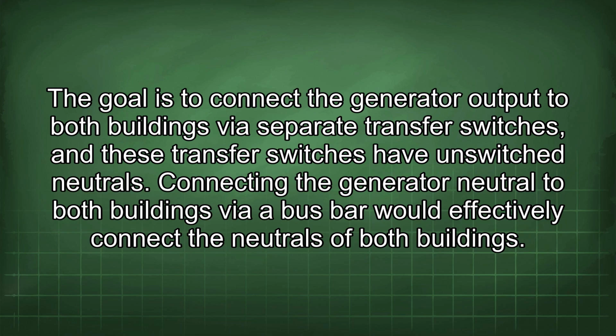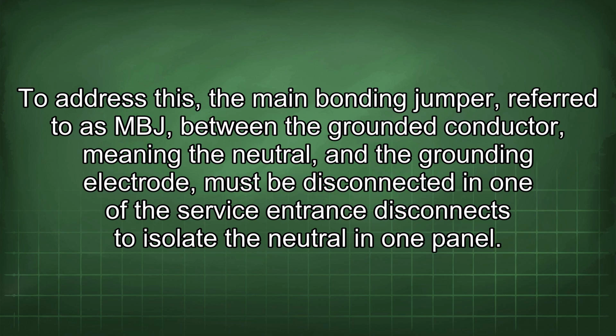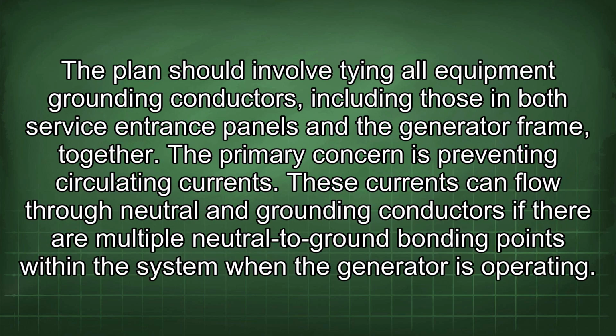Connecting the generator neutral to both buildings via a bus bar would effectively connect the neutrals of both buildings. To address this, the main bonding jumper, referred to as MBJ, between the grounded conductor, meaning the neutral, and the grounding electrode, must be disconnected in one of the service entrance disconnects to isolate the neutral in one panel. The plan should involve tying all equipment grounding conductors, including those in both service entrance panels and the generator frame, together. The primary concern is preventing circulating currents.